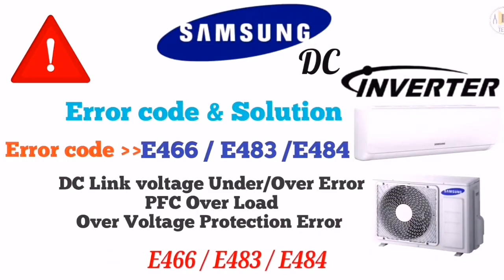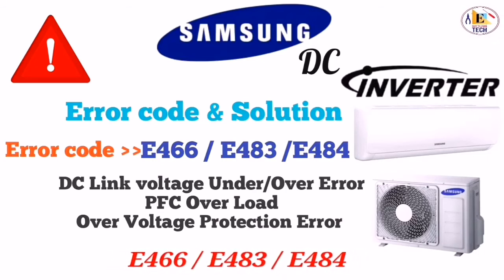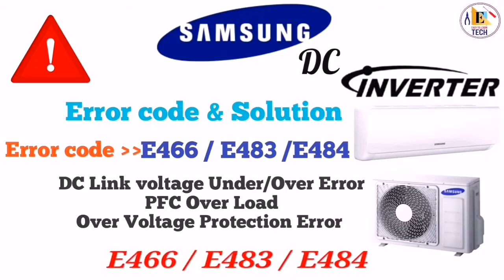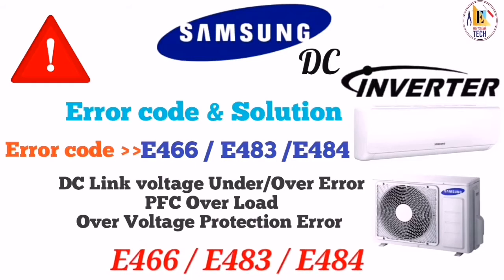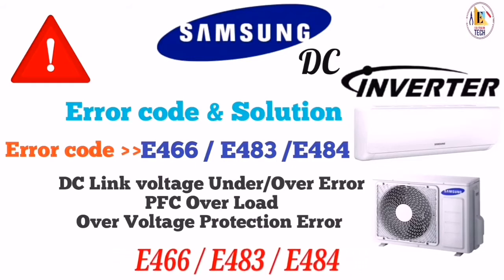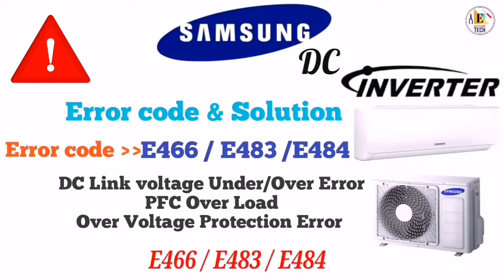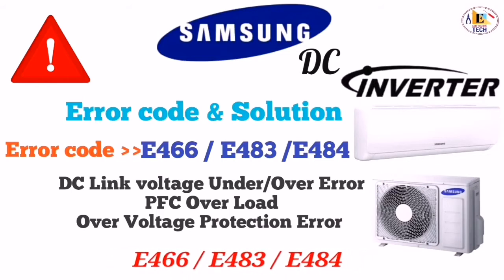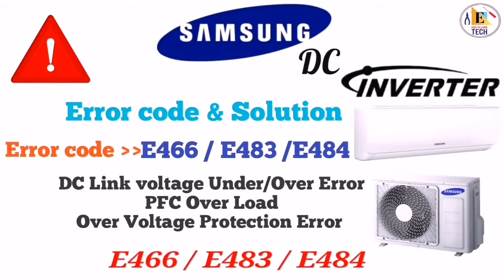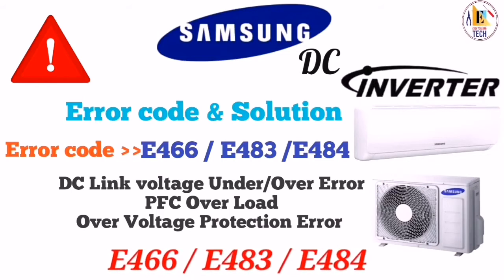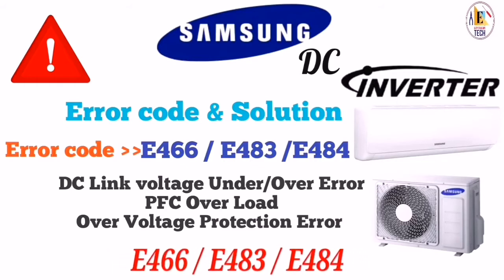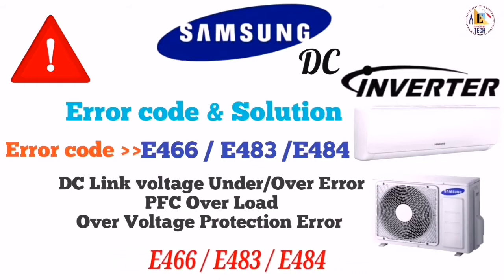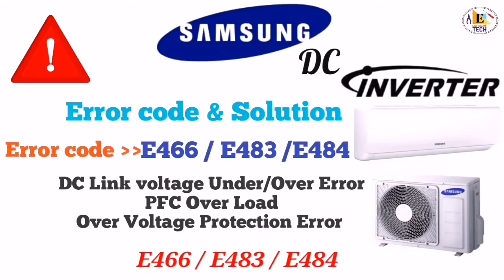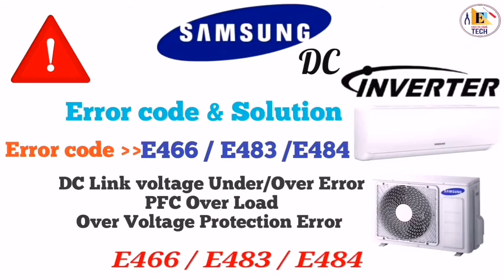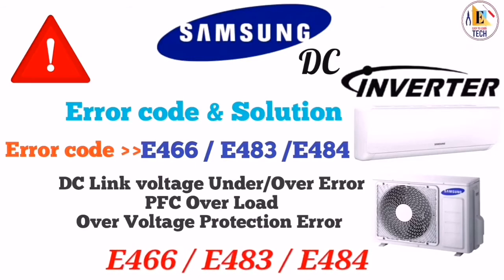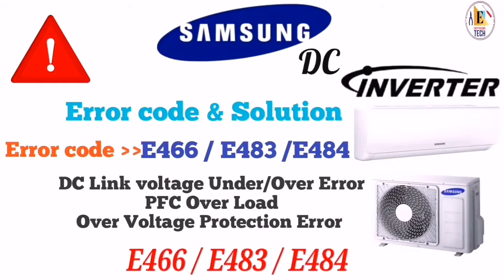Let's talk about the next error codes, E466, E483, E484. These three error codes are the same. When your LED 1 is off, LED 2 is on and LED 3 is blinking, at that time these three error codes will show as a similar blinking error. This error can be a DC link voltage under or over error, or PFC overload error, or over voltage protection error. To solve this troubleshooting, you have to follow 6 steps.